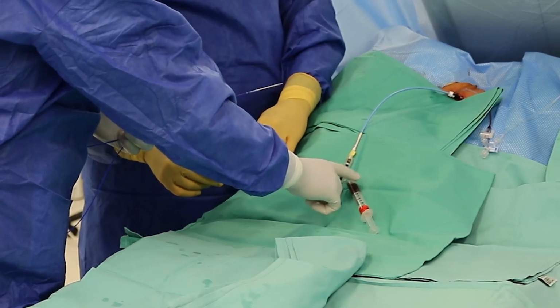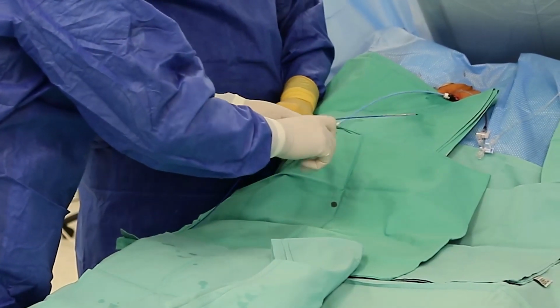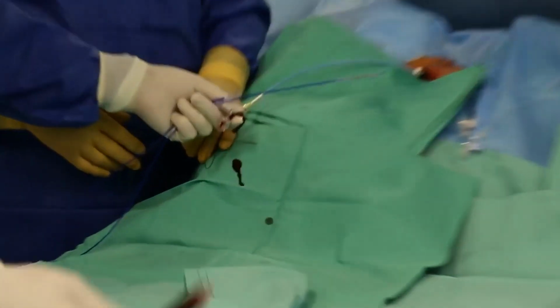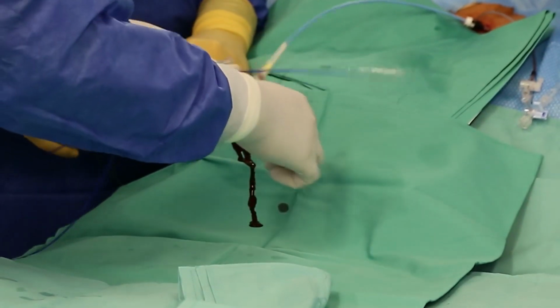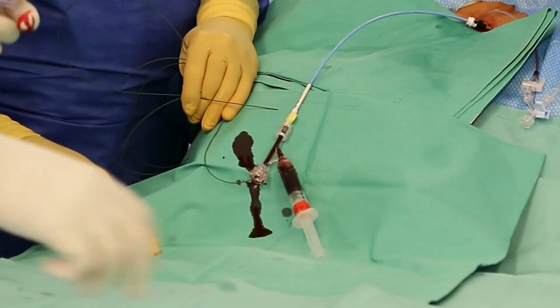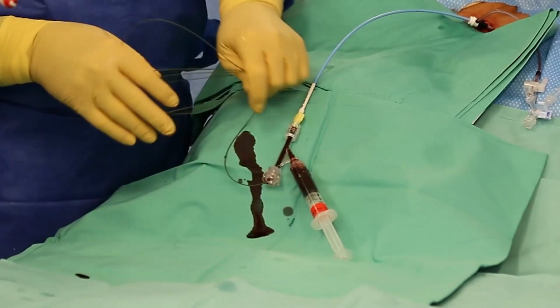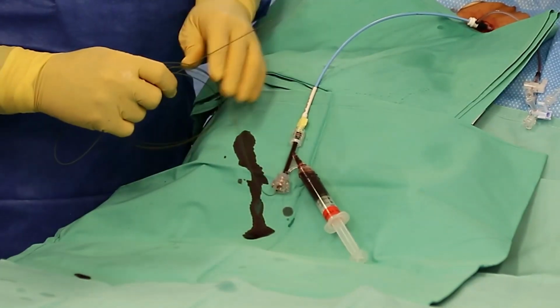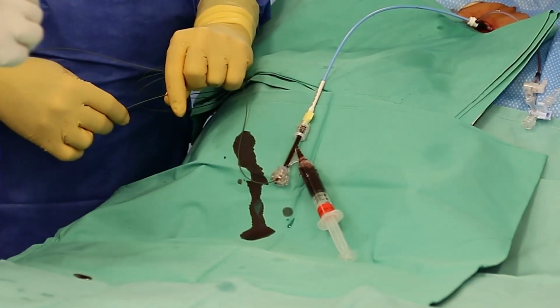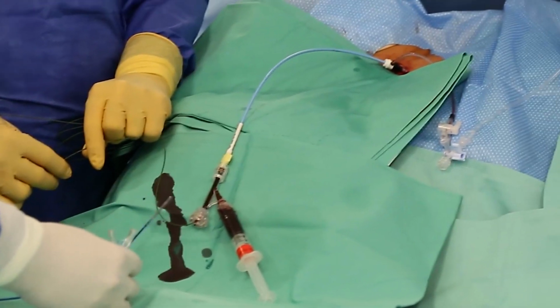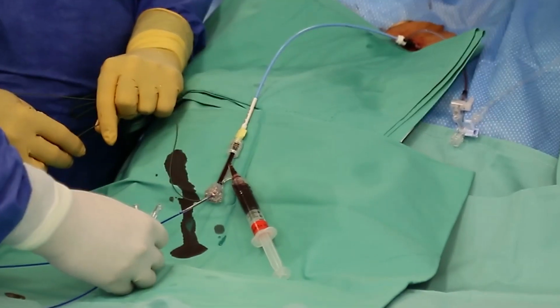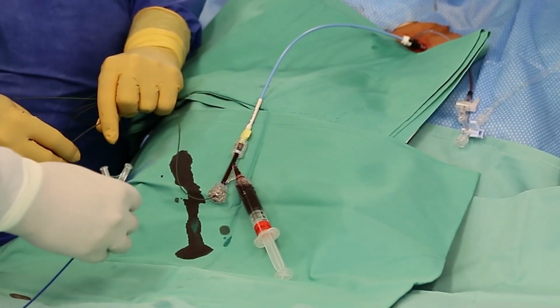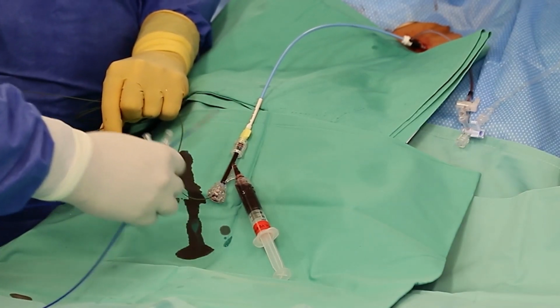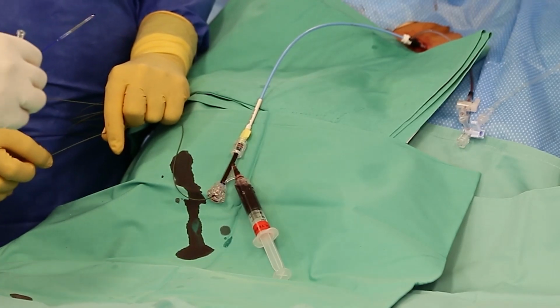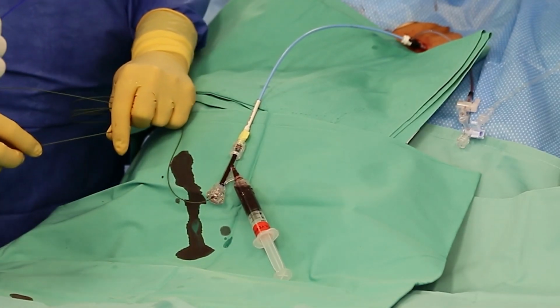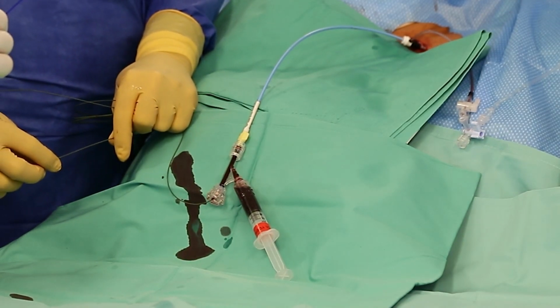At the Y connector of the guiding catheter, we will put a 10 ml syringe with contrast. So we have a 10 ml syringe with contrast. One thing that is very important when you bring the reducer through the Y connector is to open wide the Y connector, let it bleed out, so you bring the reducer into the catheter and the Y connector without any friction. This is very important because friction can move the reducer on the balloon, and if it is unnoticed, the reducer will not be implanted properly.